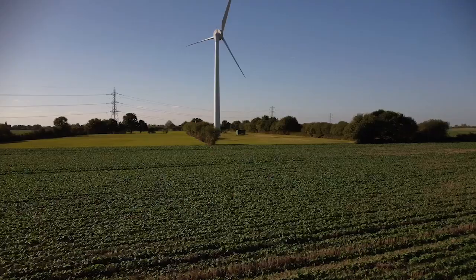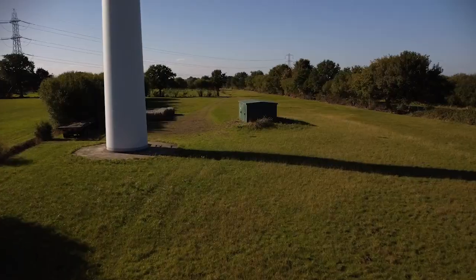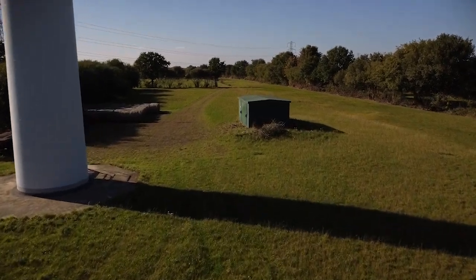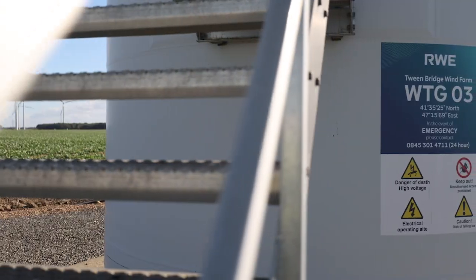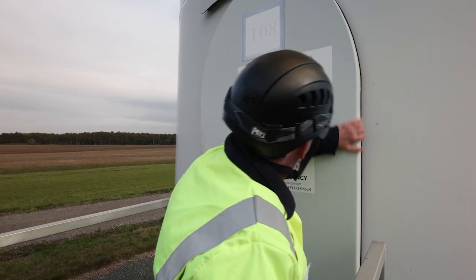So do these checks only apply to the turbines? No, some turbines have external kiosks that house the switchgear or transformer, and we have to apply the same principles when accessing them. We also have to follow the same procedures when we're accessing switch rooms back at the substation. Right, time to test you. So if we were accessing a switch room, what would we look for or check? Let me think. Well, we'd confirm that we were at the correct location and we'd check the door for signs of unauthorised access. Go on.